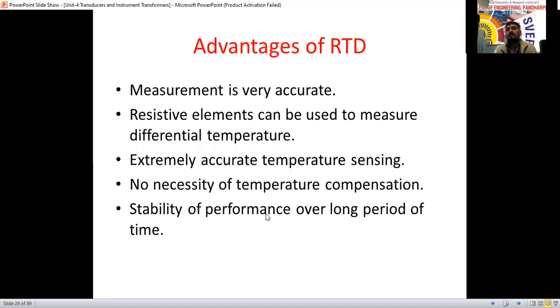So now the advantages of the resistance temperature detector. The measurement is very accurate. Whatever the temperature measurement is, it gives very accurately, in the form of resistance. The resistive elements can be used to measure differential temperatures also. It is an extremely accurate temperature sensing element. There is no necessity of temperature compensation; we have no need to compensate anything. The stability of the performance over a long period of time is the big advantage of RTD.